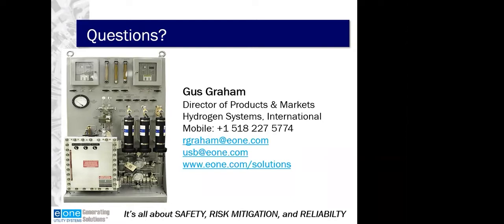Okay, and our next question for you, Gus, is how much can the purity reading accuracy be affected by oil and moisture present on the machine tubing? So we don't have a study on the exact percentage impact. We know it does have an impact, and it'll vary based on the level of contamination. So unfortunately, we don't have a study that says if you've got 1 micrometer of oil on the bead versus 2 micrometers of oil. We just know that it does have an impact.